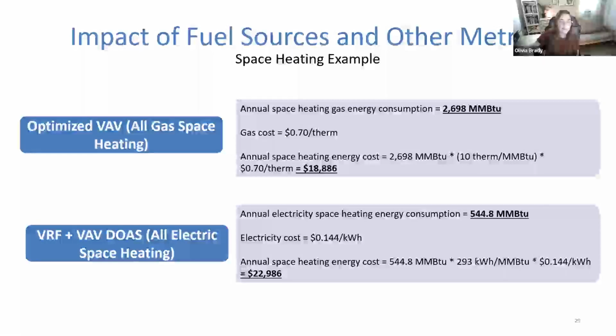Okay, so why does that performance metric matter? I'll walk through a few examples. So we know that the performance metric for 90.1 Appendix G is energy cost. So let's look at an example where the energy cost is impacted greatly by the energy or fuel source. In the first scenario I have here, we have optimized VAV with all gas space heating, and then the second scenario is VRF with VAV DOAS, which has all electric space heating.